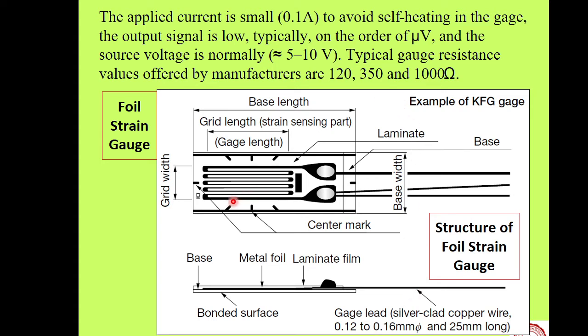So, now how is measurement done from the measurement unit and through these wires? Some voltage is applied to this strain gauge. That voltage is usually quite low, okay, limited to 5 volts. Actually, there are settings for 2 volt, 5 volt, 10 volt, etc. What happens if we increase this voltage?